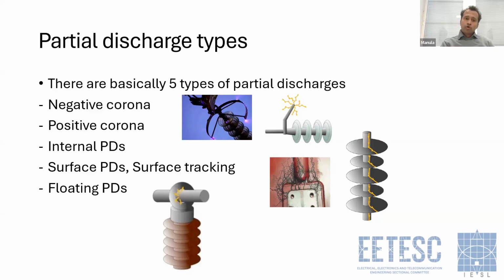This corona can happen both during the positive half cycle as well as the negative half cycle of the AC waveform. When it happens during the negative half cycle, we call it negative corona. And when the corona discharge happens during the positive half cycle, we call it positive corona. Usually negative corona is stronger than positive corona, because negative corona is caused by electrons, which have very good mobility compared to positive corona, which is caused by positive ions in the atmosphere. Those are heavier than electrons, so positive corona does not have as much mobility. So if you take the strength, negative corona would have a higher strength than positive corona.